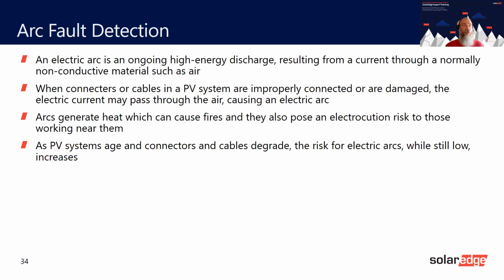It detects that there's an arc, a jump, it measures the current in the circuit. That's one of the main ways that SolarEdge works: the inverter tells the optimizers what current to produce. That then keeps in line with the 750 volts for commercial, or 380 for residential. So it uses the current as the measuring device. It knows exactly what current should be going around because it tells the optimizers what current it should be. And this is how accurate it is.